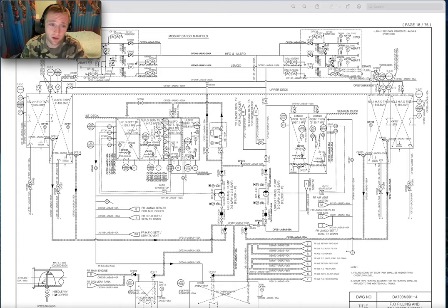piping coming here. You have also the most important, which is the overflow from the heavy fuel oil settling tank. And if you have forgotten your transfer pump in manual, it will keep filling until, okay, it also has a level alarm, but if it is never tested, it will overflow, and the last alarm, which will protect your engine room from overflowing somewhere else, will be this overflow tank.